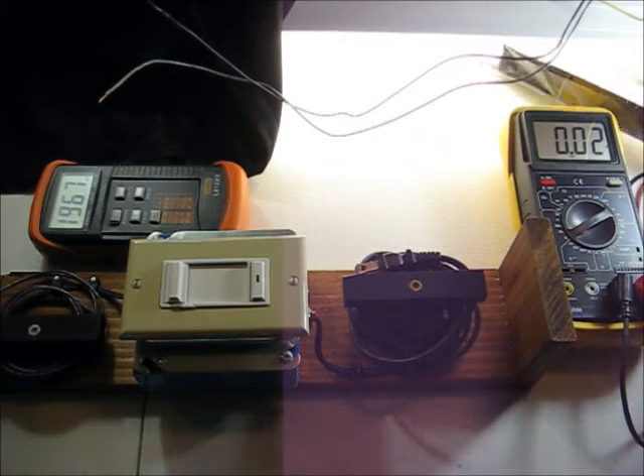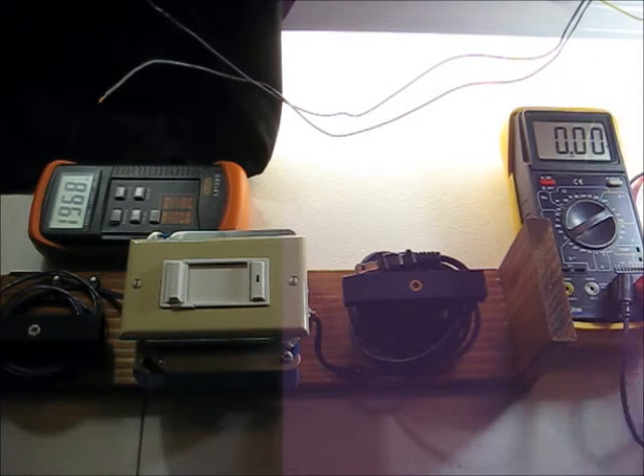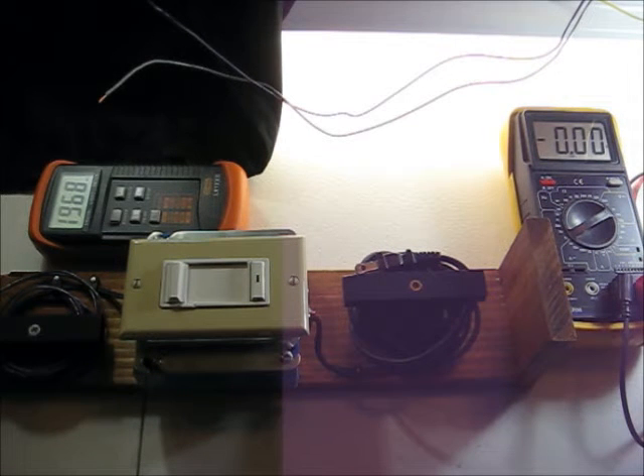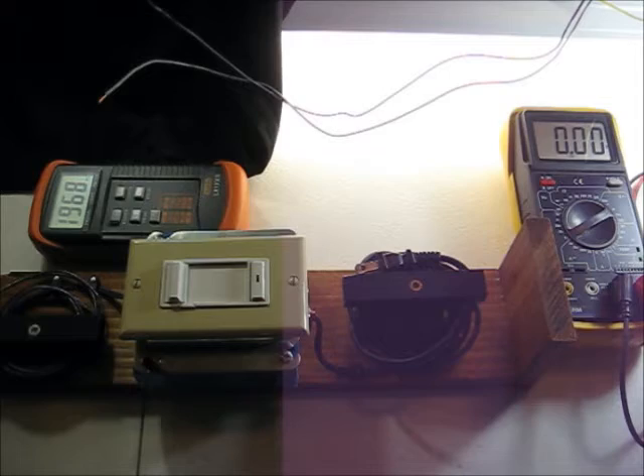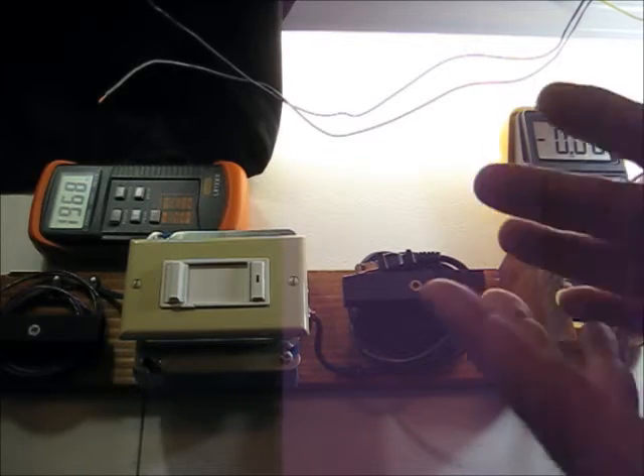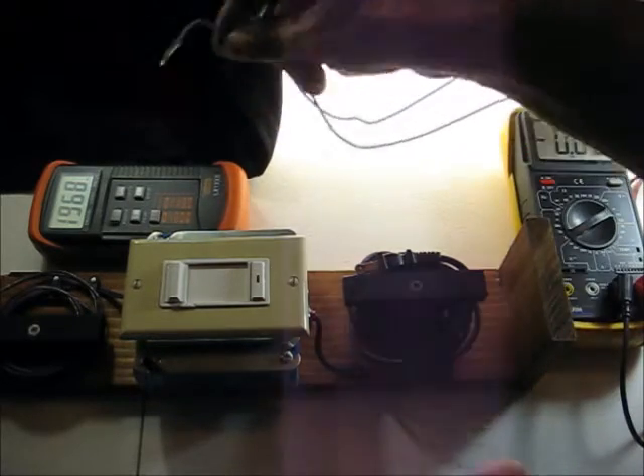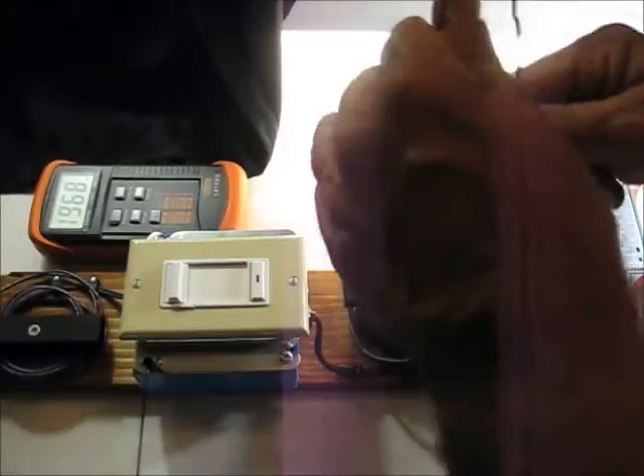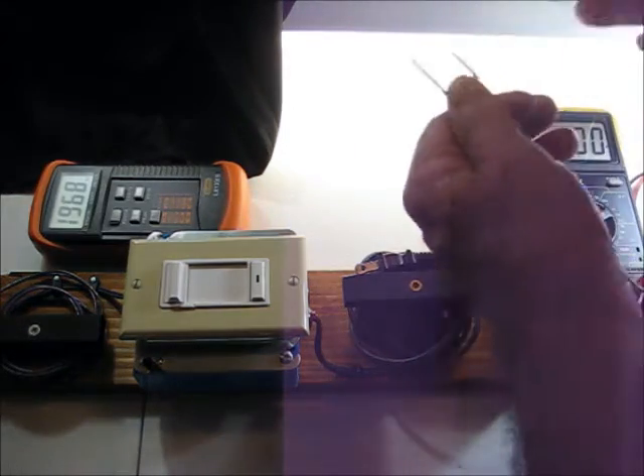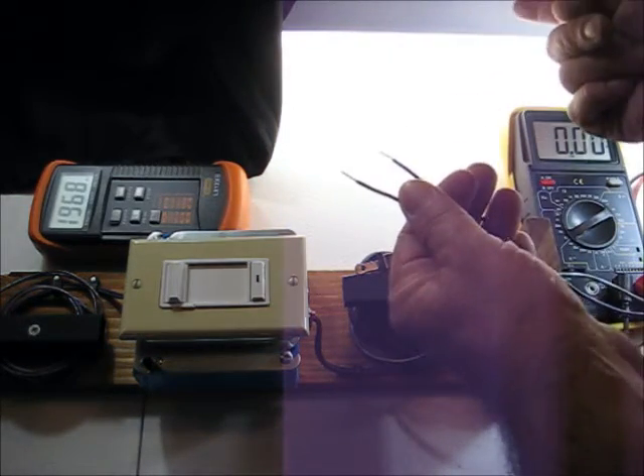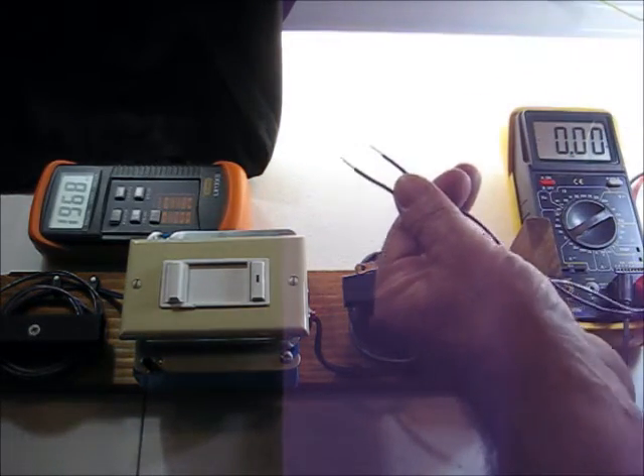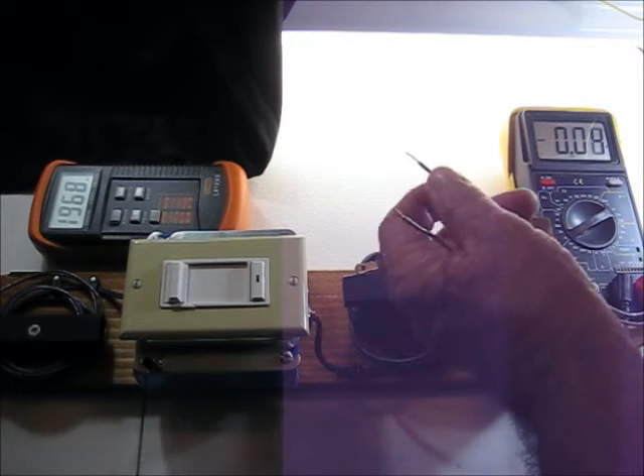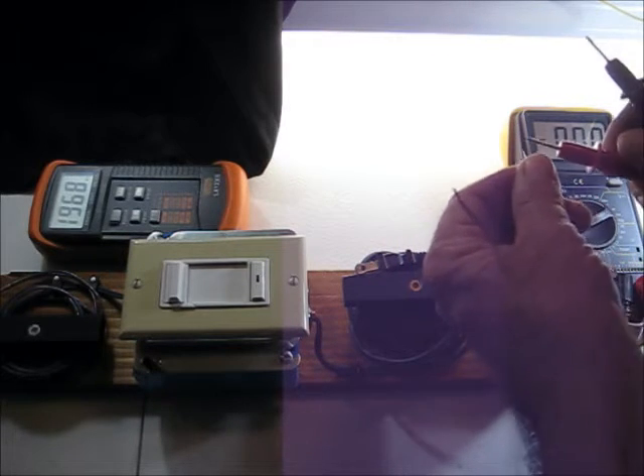And it says it can take F25 T8s, so I've installed F25 T8s. Now as a commissioning agent, when you first get on site, you're going to want to drive this at various control voltages because this is a 0 to 10 volt controller.